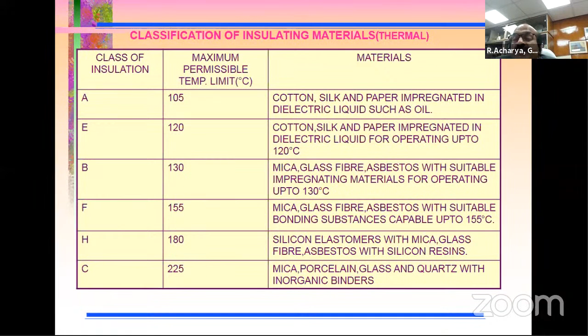So coming to the high voltage insulation system, which is applicable for large capacity machines, as I mentioned in the second slide, there are machines which in the Indian context run from anything between 1.1 kV up to 27 kV. A typical example, like 800 megawatt machines in the Telangana government as well as NTPC projects, are operating today with an operating voltage of 27 kV, right from machines which also operate at 3.3 kV and 1.1 kV.